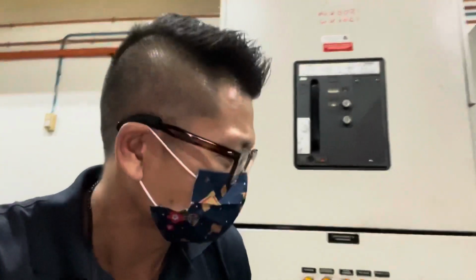It seems that when the genset cuts in, the cranking causes a lot of voltage drop to the 24 volt DC system. As the voltage drops more than a certain amount, for example to 15 volt DC or slightly lower, 13 volt DC, the contactor cannot hold anymore due to under voltage. That means the whole 24 volt system has a voltage drop. When the contactor cannot hold, it will release back. Thus, that causes fail to start, because all the control system releases their contacts due to under voltage. So that is what happened.